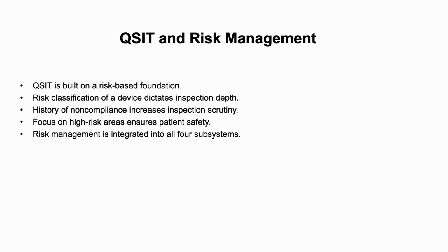At its core, QSIT is a risk-based approach to inspection. This is a fundamental principle that distinguishes it from older methods. The level of scrutiny applied during a QSIT inspection is directly proportional to the risk associated with a medical device and the manufacturer's compliance history.